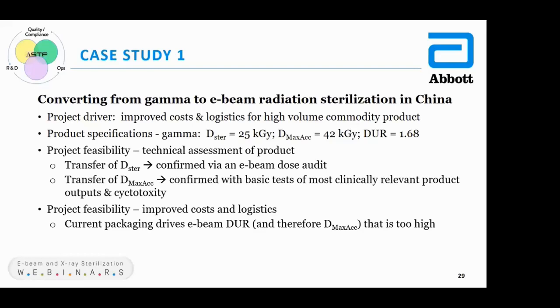So something has to be done. The options are: lower the sterilization dose. You'll see in the next case study a product where we used a sterilization dose of 20 kilogray. That corresponds to a bioburden of 45 instead of 1,000 at 25 kilogray.